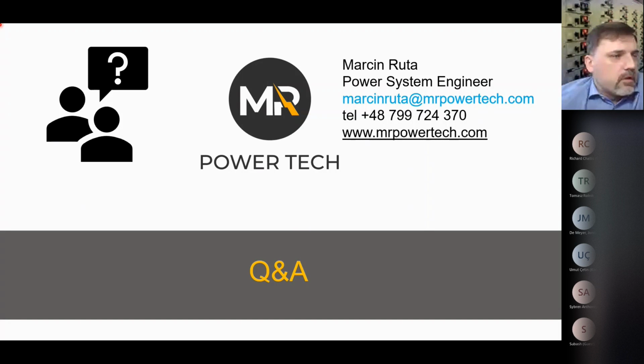Have previously used relays with multiple settings groups and switched to activate a different group via digital input. I think if this was a question from Darren, yes, I did, and did a few projects like this in my Eaton times, but also now, where generally it depends on the relay you have. The better relays will give you some ability to program multiple groups of settings, which can be activated by remote control. It might be digital by IEC 61850. So you just digitally will reprogram the relay. Of course, you have to test it before, but you might do it this way. And this might be also linked to the configuration of the network. It might happen automatically, or it might happen via SCADA system, or it might be activated by some switch. So there are a lot of options for it.